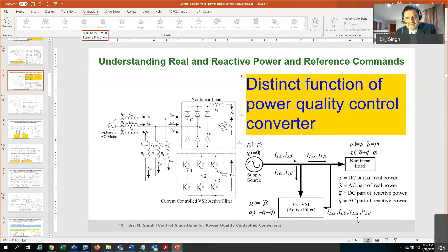So that would be the benefit. Power rating reduction is the direct benefit from harmonic elimination by passive filtering, with the rest handled by active filtering, directly benefiting the power rating reduction of these elements. As discussed earlier, switches are the delicate components most likely to fail, so making them more reliable by reducing their power rating makes the overall solution much more reliable.